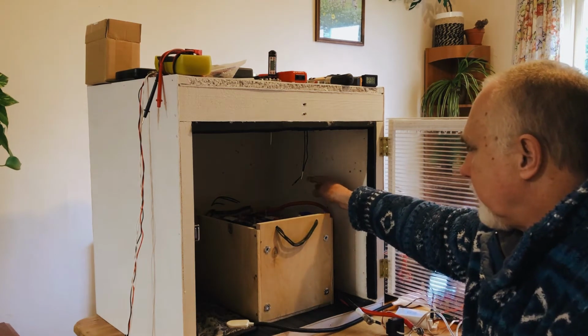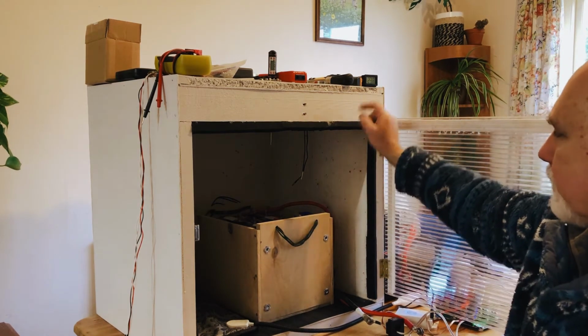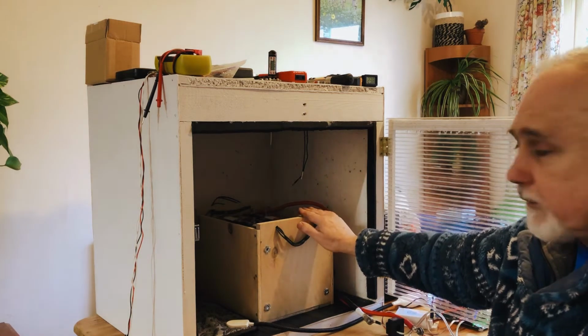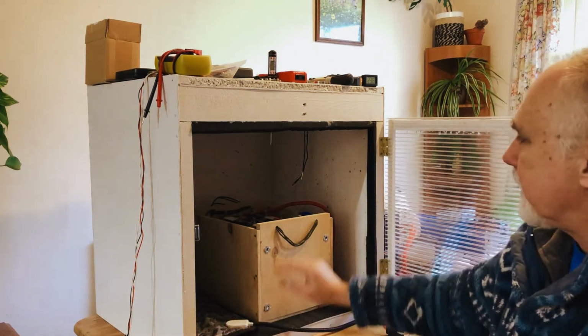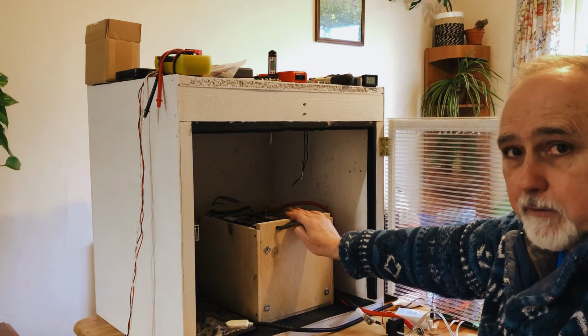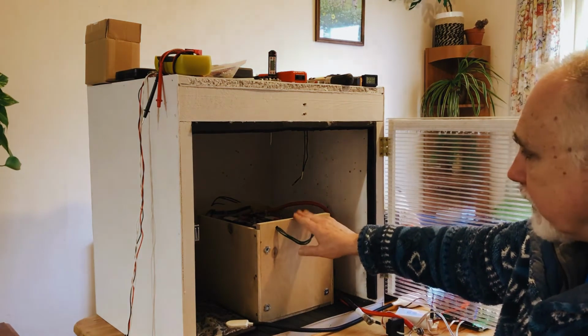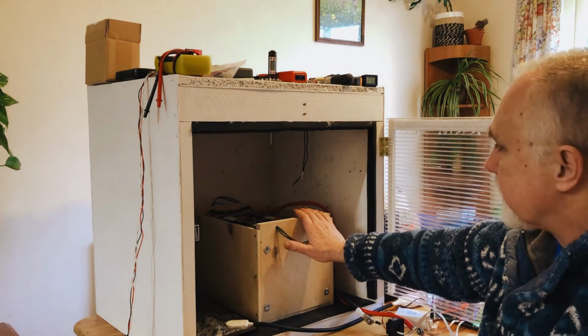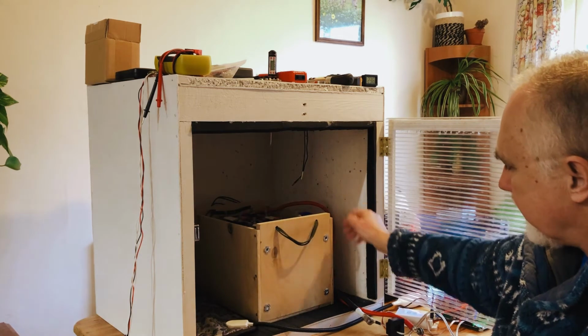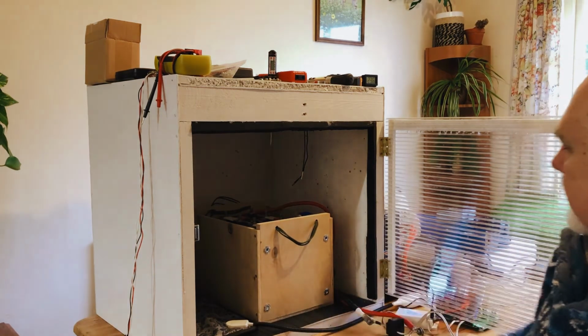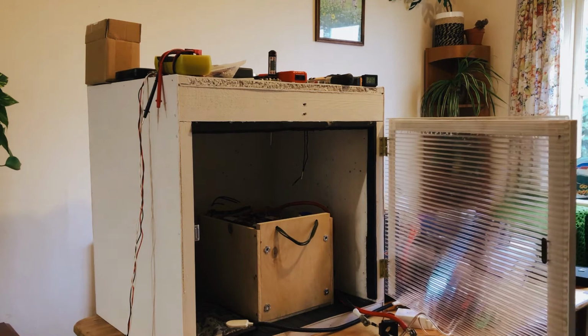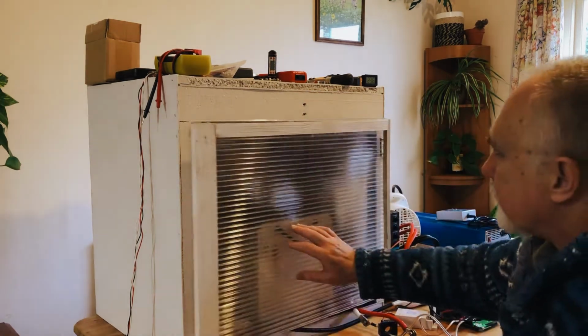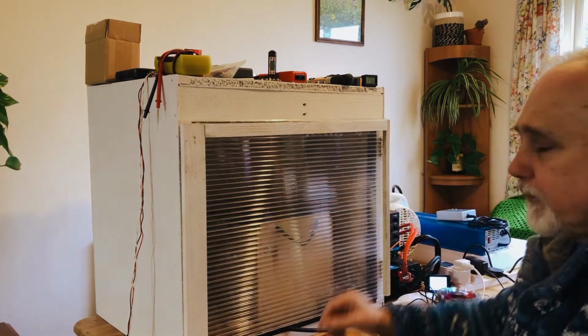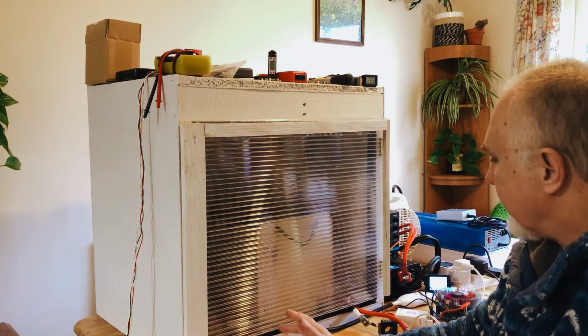There are 2 temperature probes—one to check what's happening, the other to control power to the heating pad, which turns on at about 24.5 and off at 25.5, so it sits between those two. Here's the battery pack, with the cables coming out at the bottom. We usually keep this door closed, and that brings it up to a constant 24 to 25 degrees.